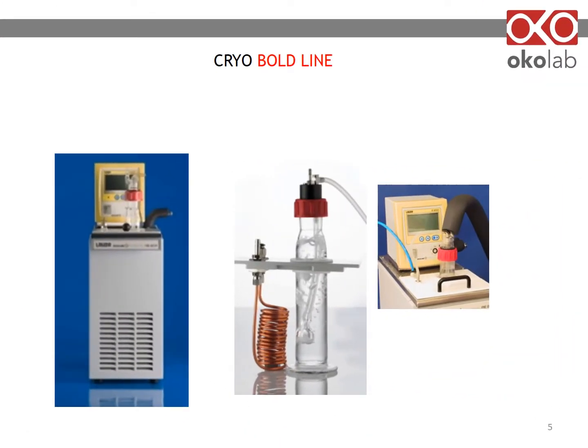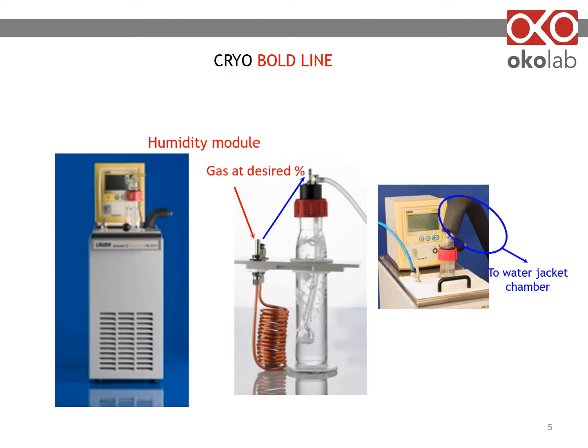A humidity module is housed inside the water bath as indicated. Gas of the desired concentration enters the water bath and runs through a coil, getting cooled or heated depending on your set point. It then flows through the humidity module where it gets humidified while maintaining temperature. Lastly, it reaches the water jacket chamber through an insulated tubing.